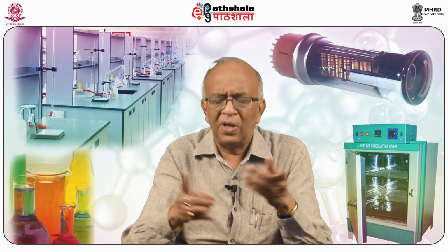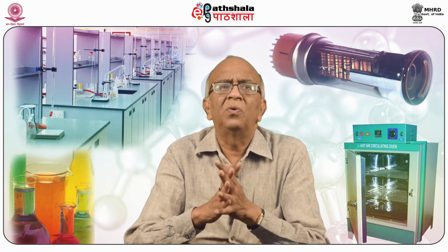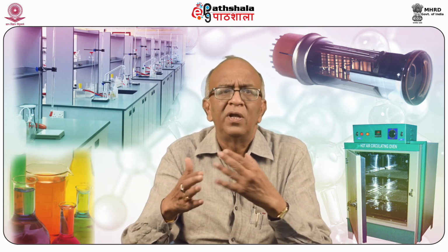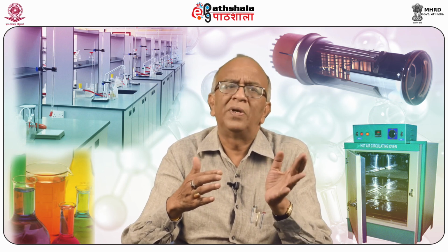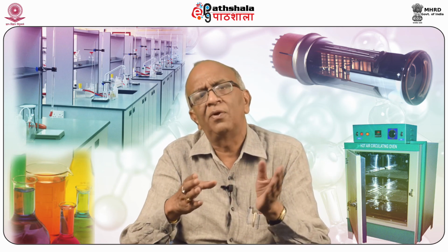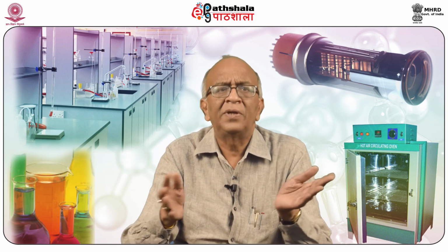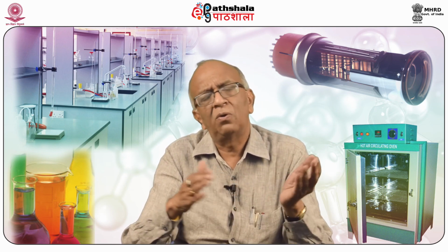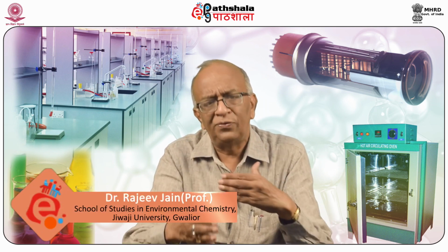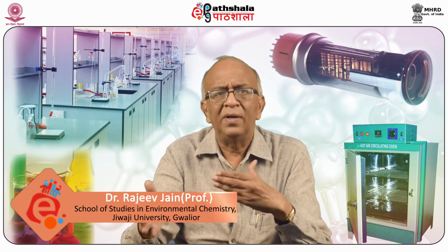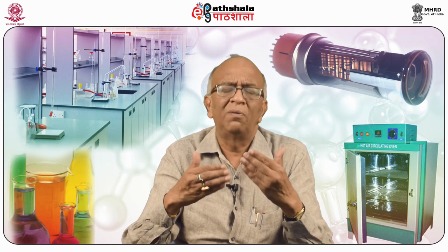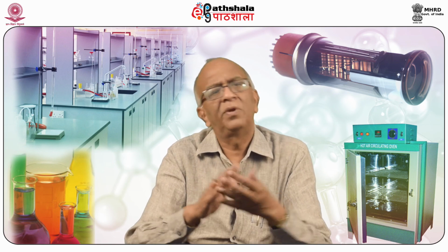The various types of errors which you observe in the monochromators and detector can be nullified if we take a double beam spectrophotometer. In a single beam spectrophotometer, there are chances of different errors arising from the source to the detector, but in a double beam spectrophotometer, because the beam splitters are there, the beam coming from the reference and from the sample is compared. So most of the errors which are likely to be there are eliminated. So double beam spectrophotometers are preferred these days.